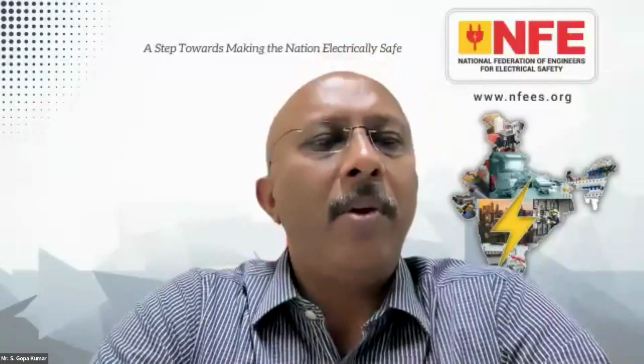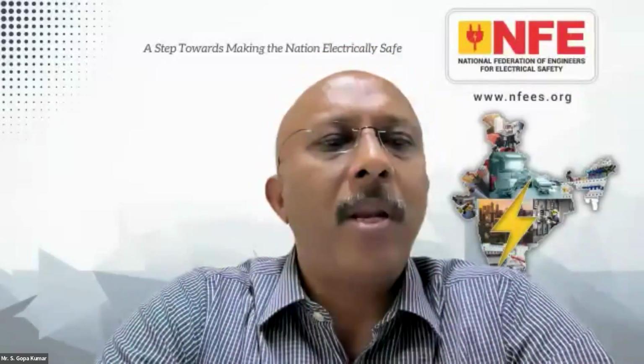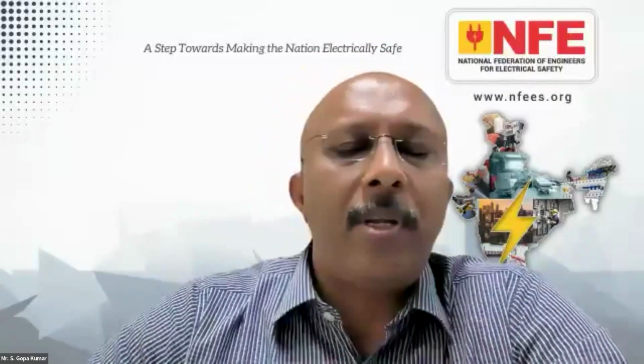Yeah, thanks. Just to add, Mr. Bhushan was also talking about this conductor, and Gopakar answered that there is a 5-wire or 5-conductor cable which is being used, and there is a dedicated earth conductor. But unfortunately, this practice has also stopped, and the cables are with 4 wires, and you have an armor coming. But the armor is unfortunately not connected, which is again putting us into a problem. Yes, the best way is to use a 5-core cable for a circuit with 3-phase, neutral plus a PE conductor, protective earth conductor.